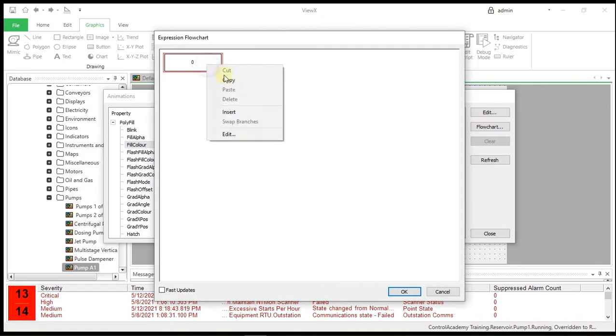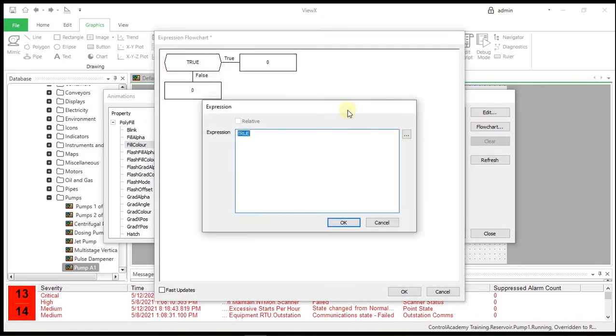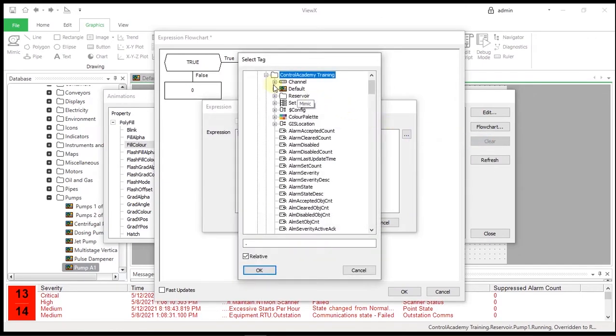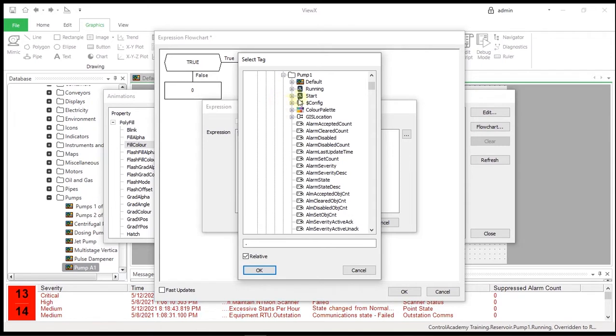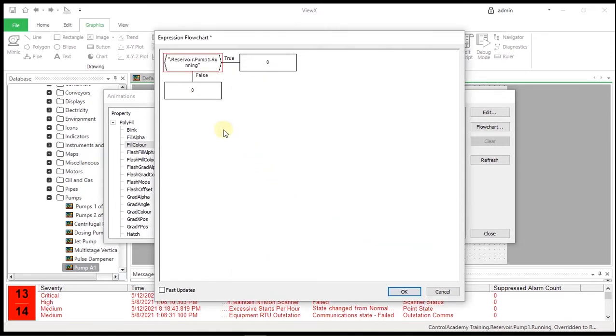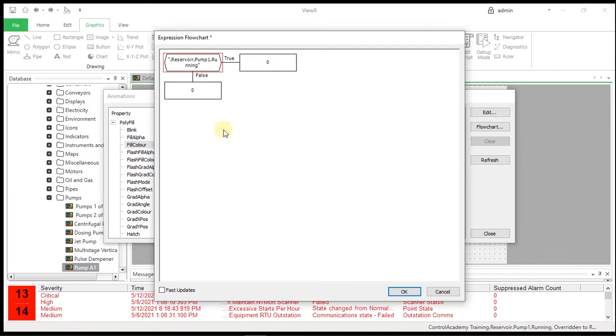Right-click on the Zero box and select Insert from the menu. Double-click the Decision block and in the window display Browse to find the running point. This is the decision point that evaluates which results should be returned. If the expression in this block is evaluated as True, the True branch is executed. Similarly, if it's a False value then the False branch will be executed. Note that if we didn't select a property from the point, that means by default the selected property is the value.